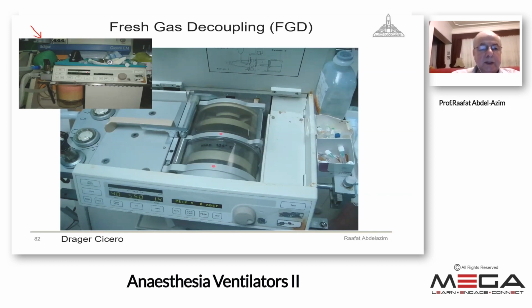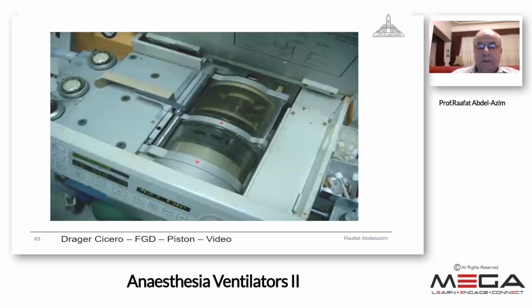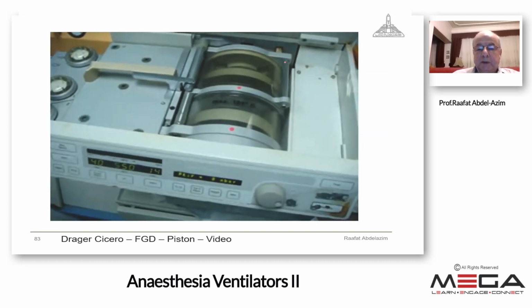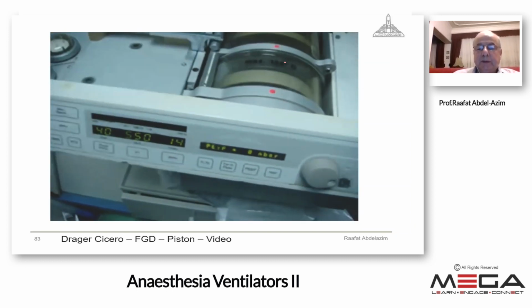When I cannot see the ventilator here, I cannot see bellows. The bellows is replaced by what is called a piston. When I remove the cover of the ventilator, I can see this piston. By activating the video, you can see the piston moving in a horizontal movement. It is mechanically operated. It is not pushed by the driving gas. You see now the video. Now the piston is moving, delivering what is inside the piston into the patient's lung.